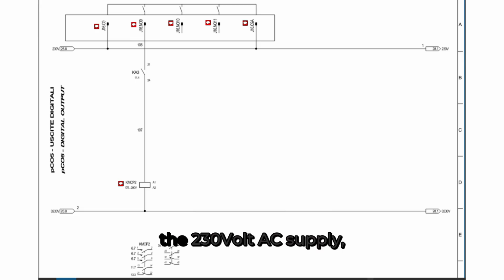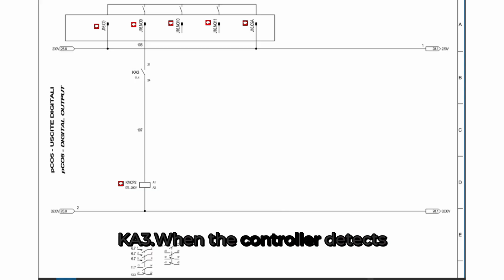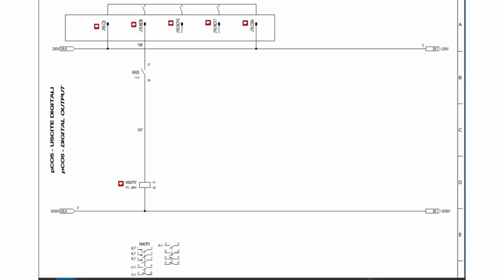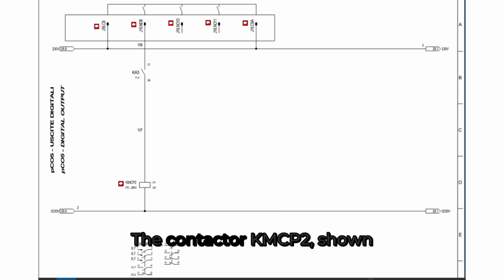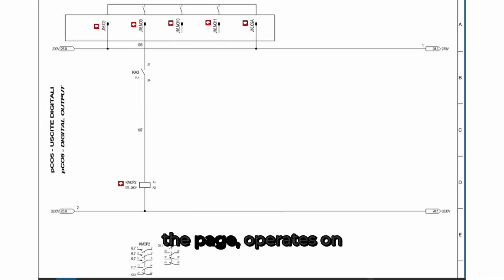At the top of the page, we see the 230-volt AC supply feeding into the controller's relay output bank, identified as J16. In this diagram, the relay output J16.NO9 is connected through relay KA3. When the controller detects a demand for cooling or heating from refrigeration circuit 2, it energizes KA3, closing its contacts and completing the circuit to KMCP2, the compressor 2 contactor coil. The contactor KMCP2, shown near the bottom of the page, operates on 230V AC and serves as the primary control point for the second compressor motor. When energized, it closes its 3 power contacts, allowing full 3-phase voltage to reach the compressor motor terminals.